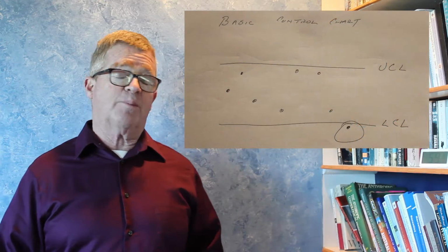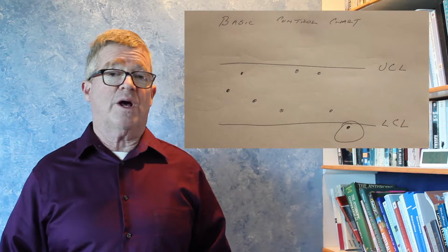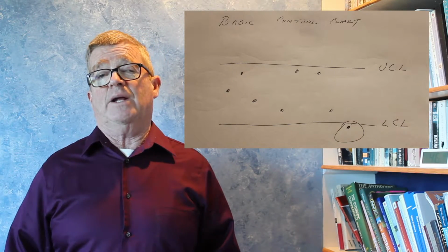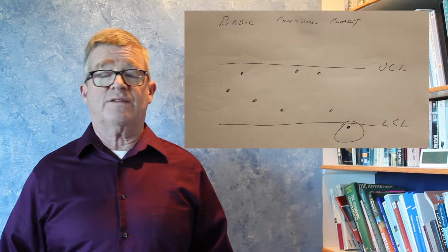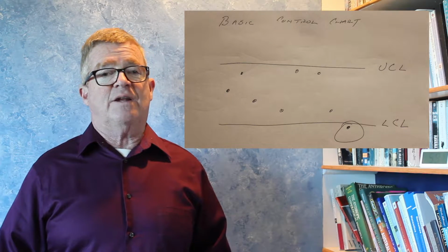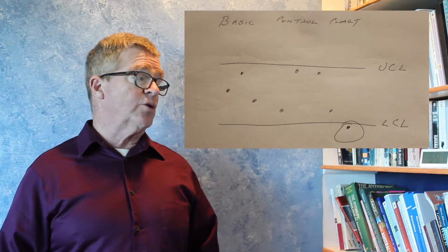Now, this is a black box. It's not black magic. The tools that Dan suggests are used every day in many, many different industries. In addition, in Dan's article, he uses control charts to plot the performance of his two sensors compared to each other. And here's the world's simplest control chart, just to show you what's going on. Dan calculated upper and lower control limits for his two data sets, and as long as the data doesn't exceed one of those limits, we can be sure that we're not seeing one of the failures that I described earlier.